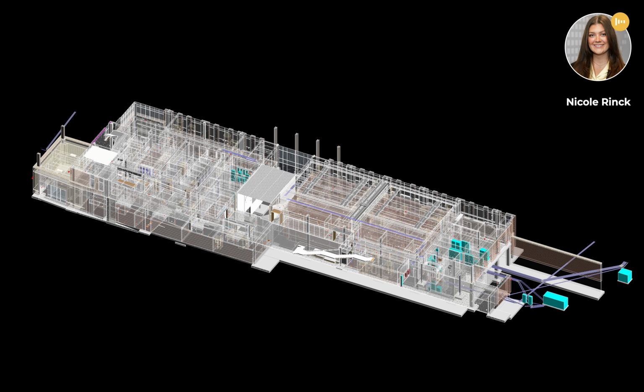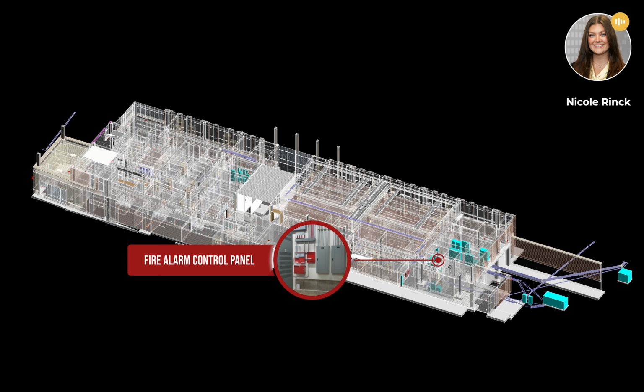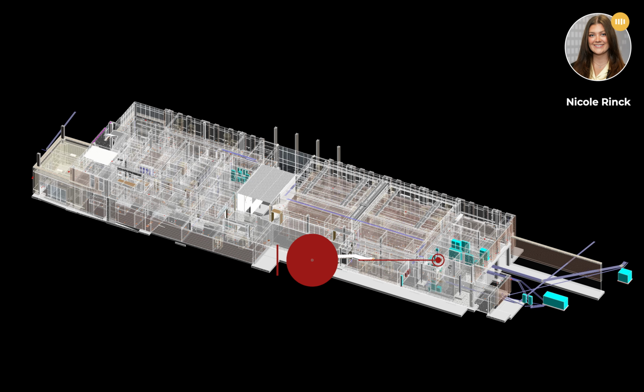In the event of a fire, detection needs to be provided so that building occupants can stay safe. This building has the main fire control panel located in the main electrical room. Through programming, all of the fire alarm devices are monitored on this panel. Fire alarm devices can fall into 2 different categories: detection and notification.